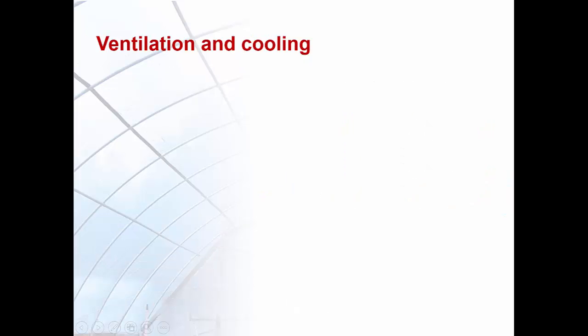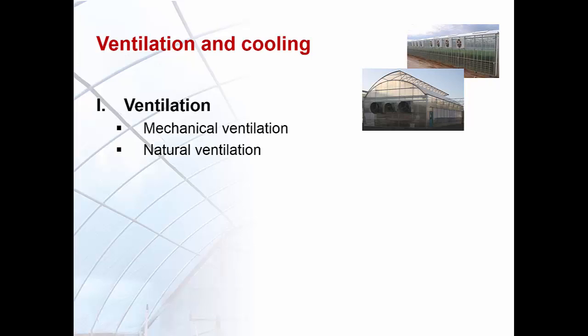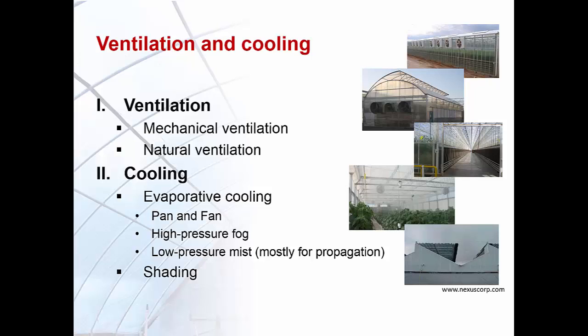Typical methods to prevent excessive temperature rises in greenhouse systems are ventilation and cooling. Ventilation can be achieved using mechanical ventilation with fans or by natural ventilation using roof and side vents. Common cooling methods include evaporative cooling systems such as pad and fan, high pressure fogging systems, and low pressure misting systems, as well as shading with internal and external shade curtains.